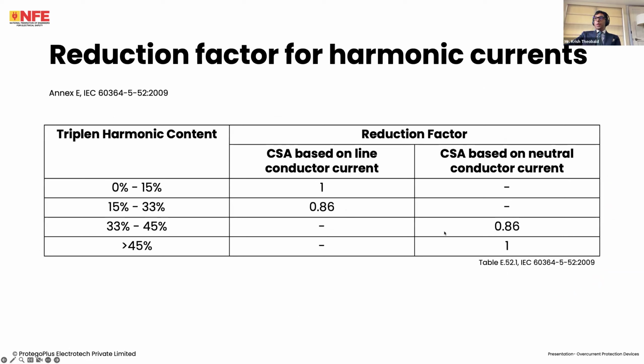Now, like I said, this is the value to choose when we have triplen harmonic content between 15 to 33%. As you can see, if there is 33% triplen harmonic distortion, the neutral conductor current is 99% of the line conductor current, so almost the same as the line conductor current. In these cases, because we are effectively having a fourth grouped conductor, this 0.86 value takes into account the presence of the fourth grouped conductor.